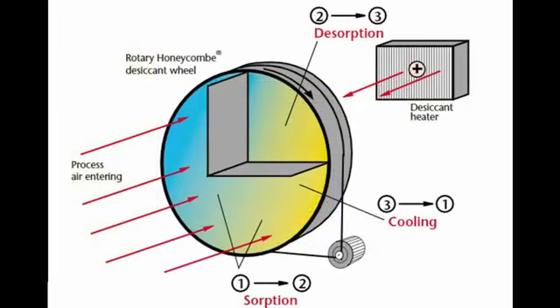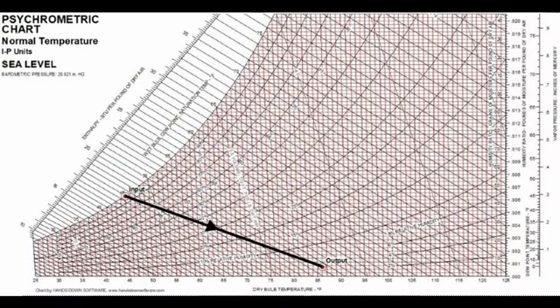In DHU12, a slow-moving desiccant wheel is heated by a separate stream of reactivation air, which heats and dries the top section of the wheel. The process air then moves slowly through the bottom section of the wheel, which absorbs moisture from the air. This decreases the absolute humidity and increases the temperature of the air. DHU12 has the capacity of outputting a leaving humidity ratio of 5.2 grains per pound in the processed air. This psychrometric chart shows the state of the air as it goes through DHU12. The air enters at a higher humidity ratio and lower temperature, then as it moves through DHU12, the humidity ratio decreases as the temperature increases.